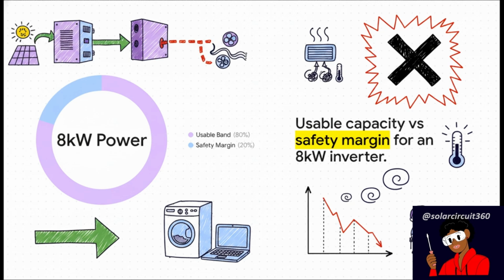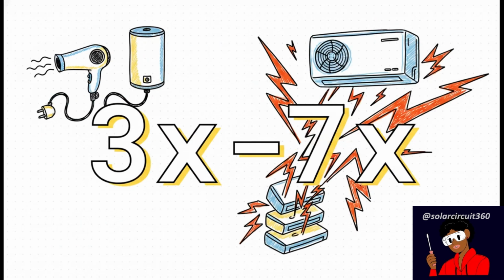That remaining 1.6 kilowatts acts as your vital safety margin and derating buffer. It accounts for the harsh reality that ambient heat, maybe some poor ventilation in the utility closet, and basic wiring losses will reduce your inverter's capacity in real time. Now picture this: your usable band is sitting right around that 6.4 kilowatts.